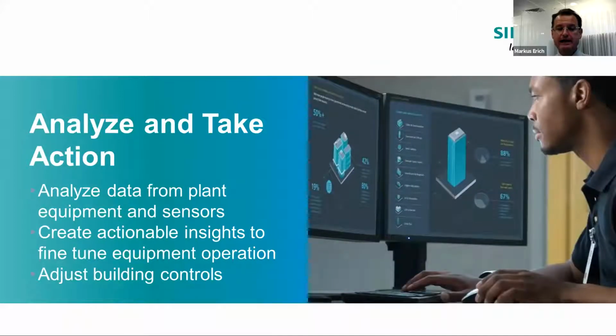Once we had connected and collected the data, the most significant step was to analyze it from all the plant equipment and sensors, to create actionable insights and fine-tune the operation of the building and adjust the controls. That was done by the Demand Flow software.